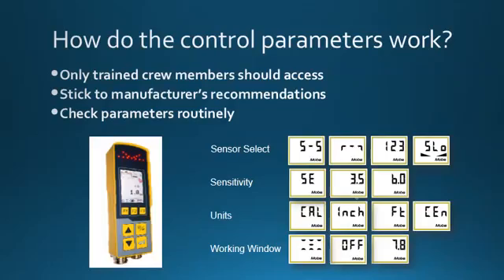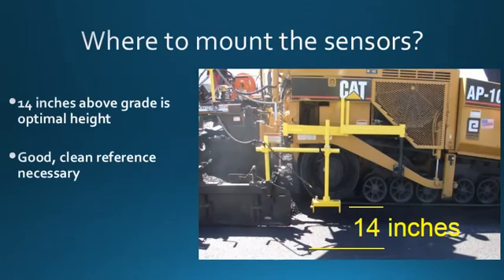The second point is to stick to the manufacturer's recommendations and guidelines. Having said that, this is something that should be checked routinely, and especially when the system doesn't seem to be performing quite right. Grade sensor mounting is very important. An ultrasonic sensor is using reflected sound waves to measure the distance to grade. And because the speed of sound in air is affected by temperature, sudden changes in air temperature will adversely affect the accuracy of the measurement.